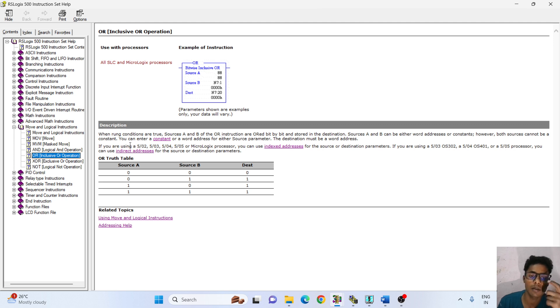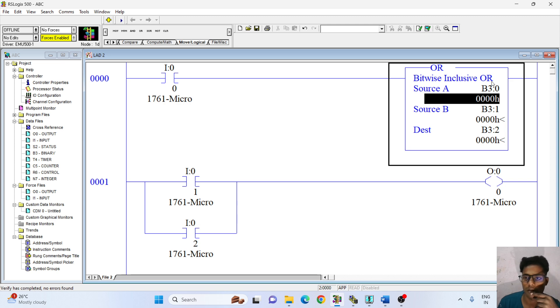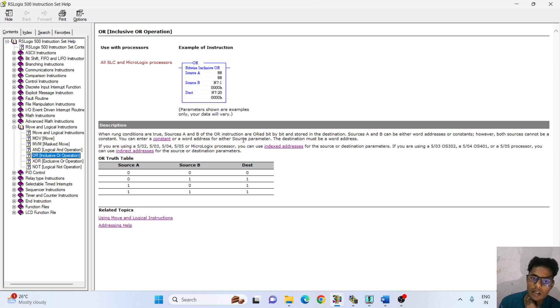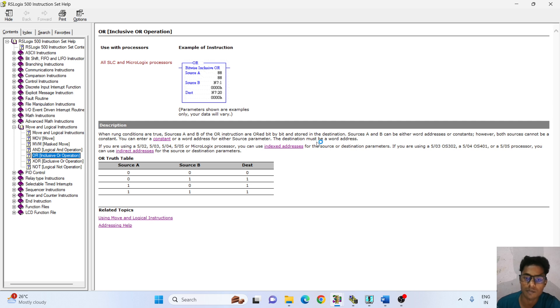Both sources cannot be constant — you can enter a constant for one source parameter. The destination must be a word address. If you are using SLC 5/05, 5/03, 5/04, or a MicroLogix processor, you can use index addressing or indirect addressing for the source or destination parameter.